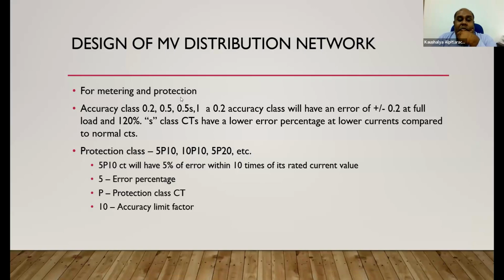Accuracy class typically 0.2, 0.2s, 0.5, 0.5s, 1. If it is a 0.2 accuracy class, that means you have plus or minus 0.2 error at full load and 20% more from the full load. If it is an S class CT, you have a much lower percentage error at lower currents compared to the normal CT. Protection classes can be 5P10, 10P10, 5P20, which means 5% error within 10 times its rated current value. 5 denotes the error percentage, P for protection class, 10 for the accuracy limit. You have 5P20, 5P10, 10P10, and so on.